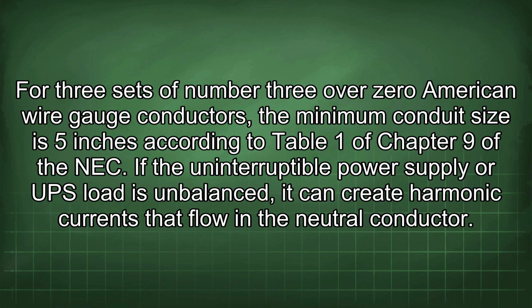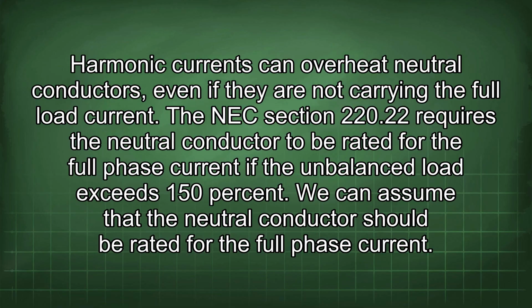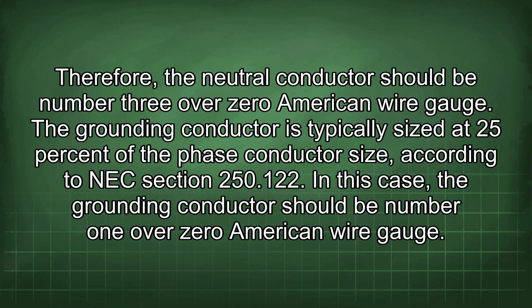If the uninterruptible power supply or UPS load is unbalanced, it can create harmonic currents that flow in the neutral conductor. Harmonic currents can overheat neutral conductors, even if they are not carrying the full load current. The NEC section 220.22 requires the neutral conductor to be rated for the full phase current if the unbalanced load exceeds 150%. We can assume that the neutral conductor should be rated for the full phase current. Therefore, the neutral conductor should be number 3/0 American wire gauge.